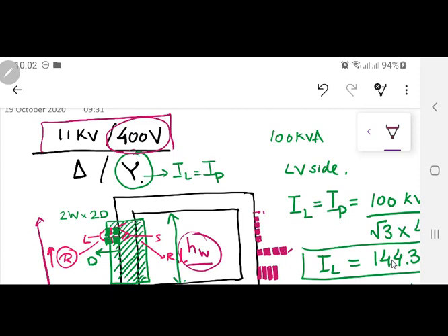Nowadays air conditioners are inverter based, so they take current relatively gradually, but previously ACs would take dramatically high current, 8 or 9 amperes in the starting, or maybe even larger than that. So what will happen is that the 400 volt winding on the transformer is going to be subjected to high switching impulses.